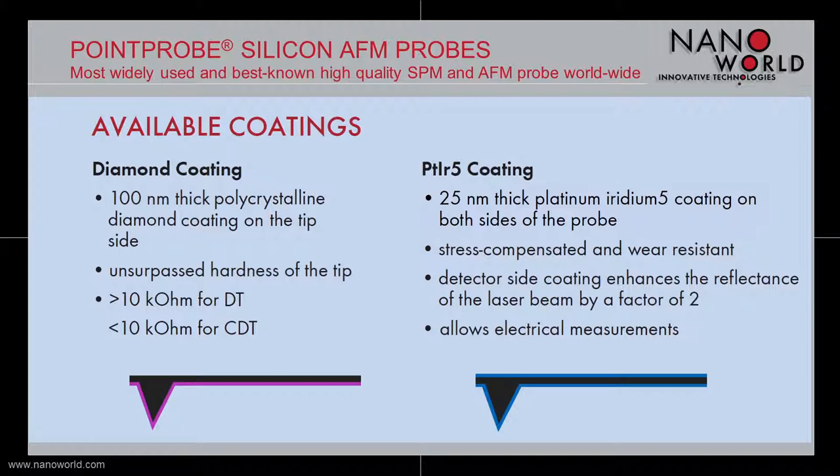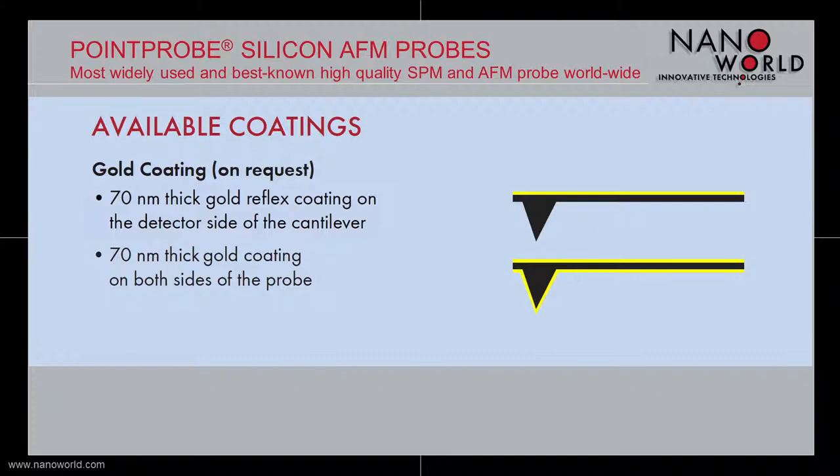The diamond coating gives the tip an unsurpassed hardness. For electrical measurements, a 25 nm thick platinum iridium 5 coating is deposited on both sides of our Point Probe cantilever. The platinum iridium covered cantilever is stress compensated and has a higher wear resistance. The platinum iridium coating on the back side also enhances the reflectance of the laser beam by a factor of 2. On request, it is also possible to coat our Point Probe silicon cantilever with a 70 nm thick gold layer, either only on the detector side or on both sides of the cantilever.